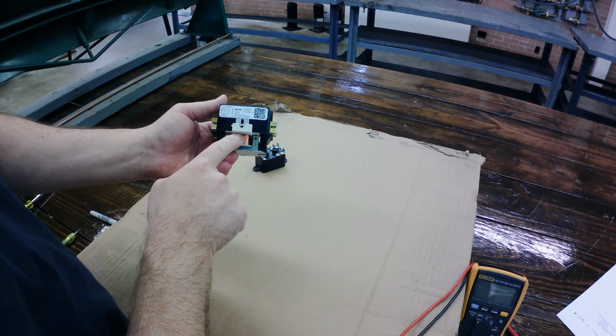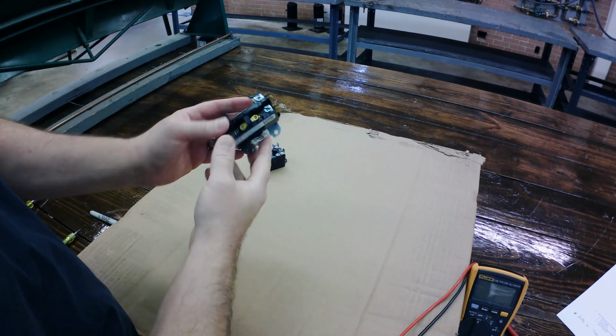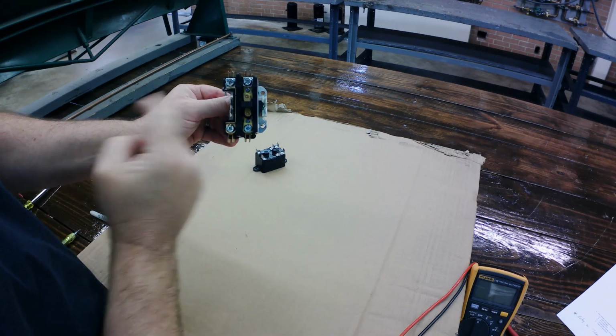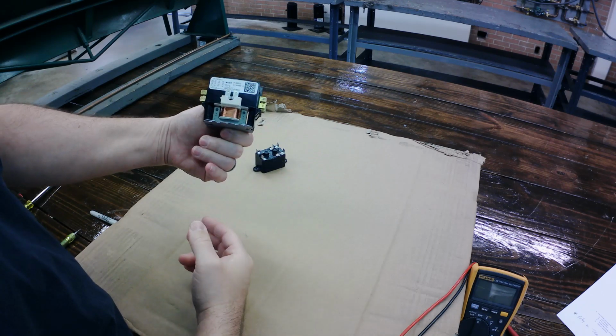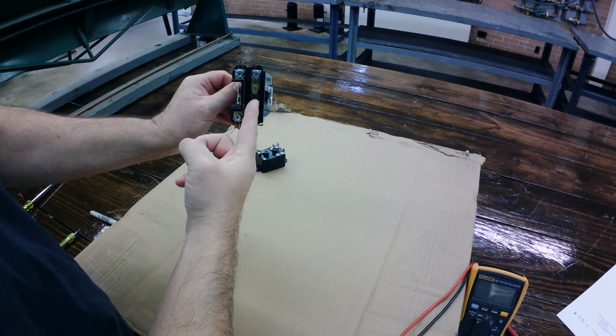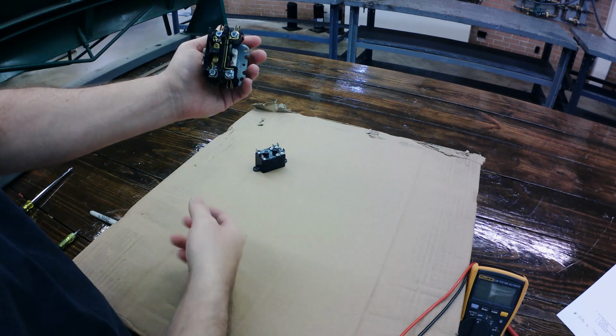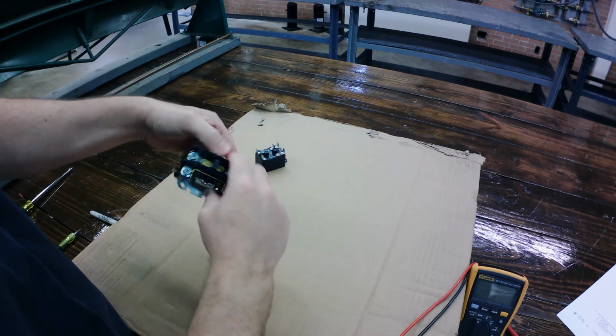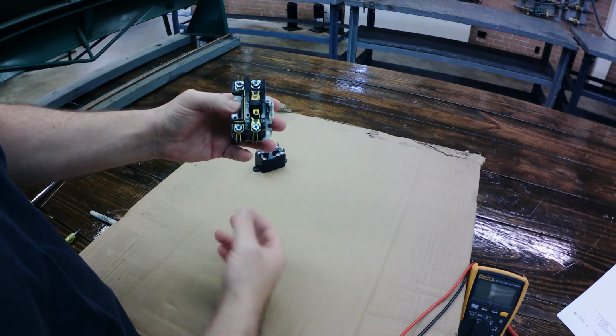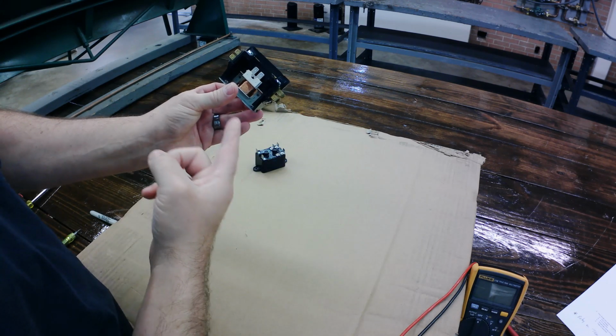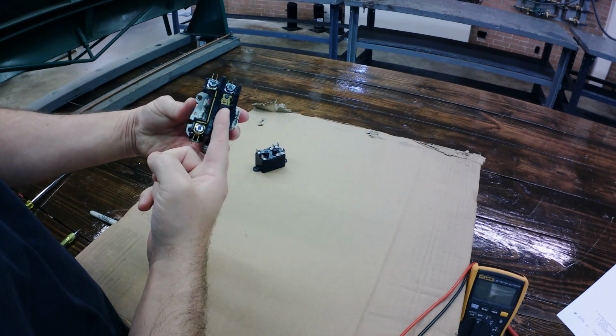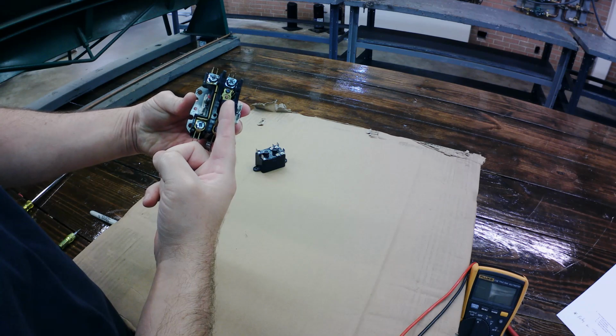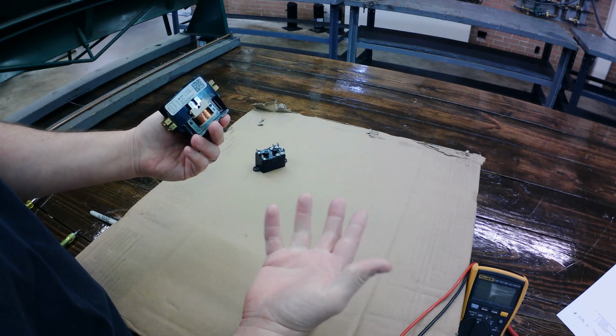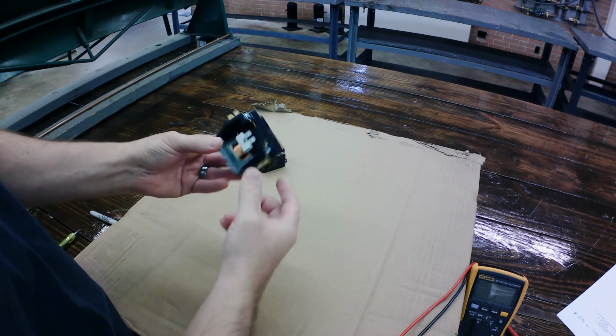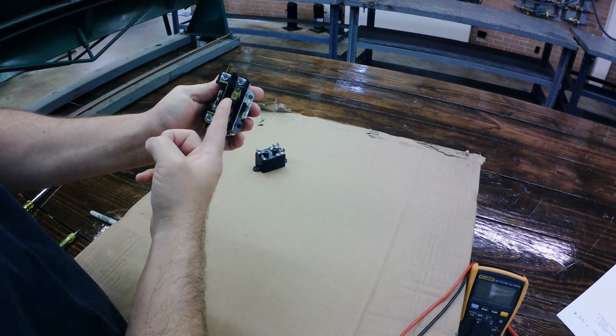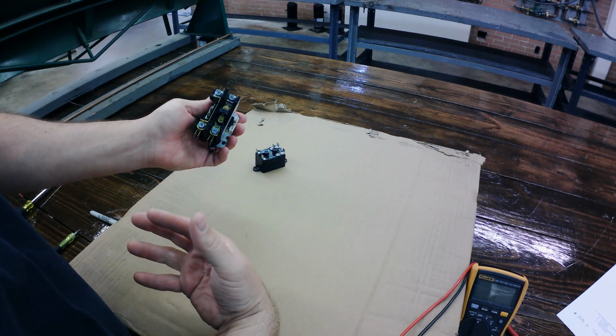And when that coil gets powered, it energizes, and it's going to cause this switch to react. And like I said, it's real simple. This is a one pole contactor. It's only a switch in one side. Depending on which way you hold it, it's the left or the right, no big deal. But it is a big deal. You should replace it just like it's in there. But don't forget that this is a two-part component, the coil and the switch. The switch shouldn't open or close until the coil does something to cause that reaction. So the thermostat controls the coil, the coil controls the switch, and then the switch turns on the motors or turns off the motors. So too easy.